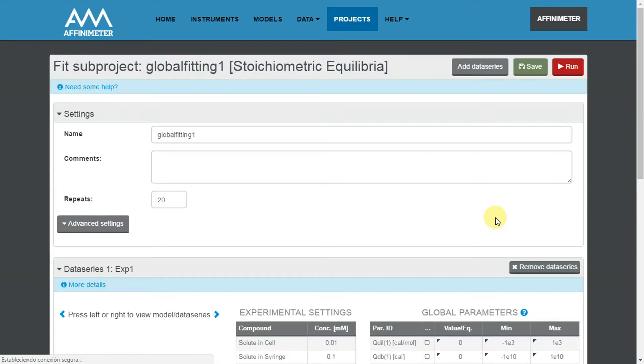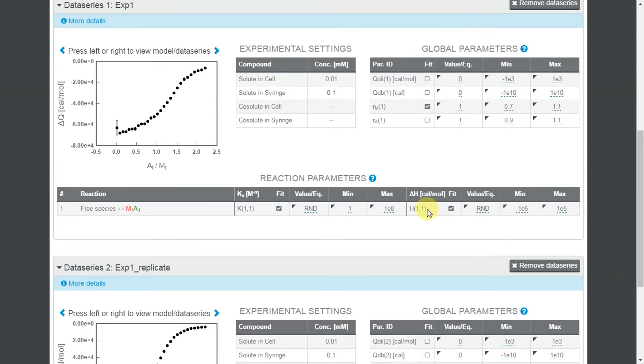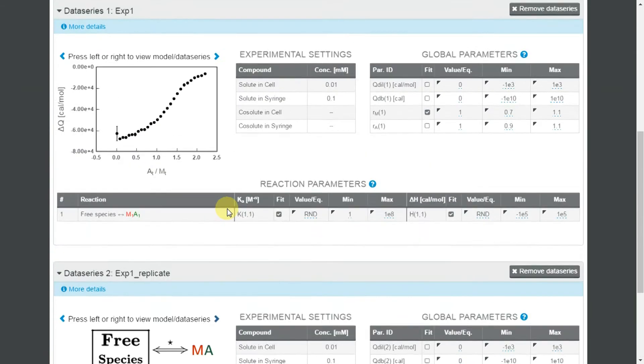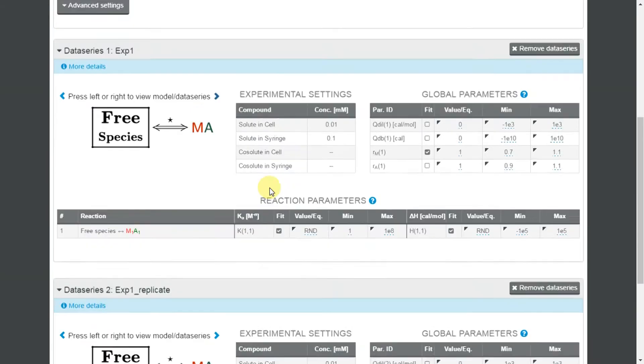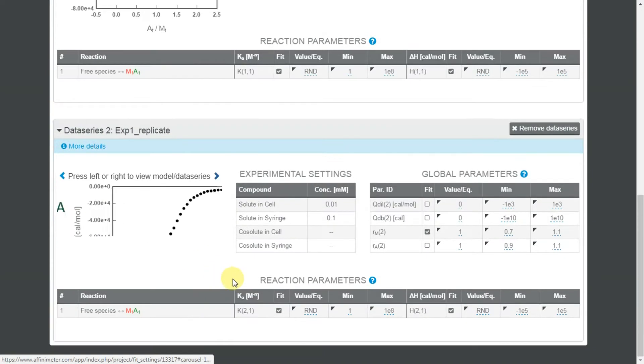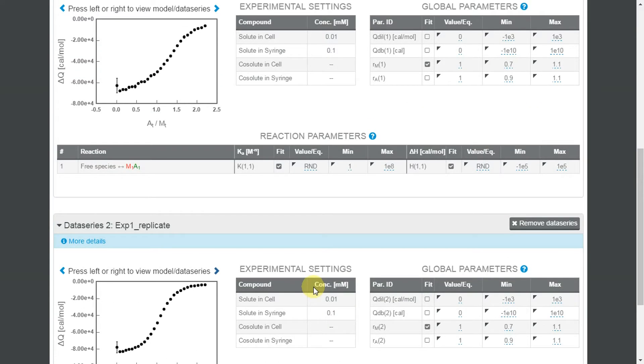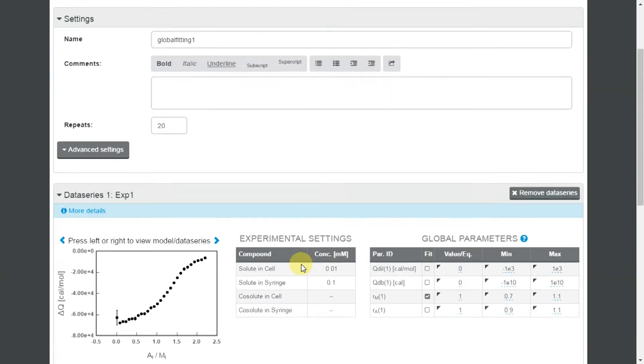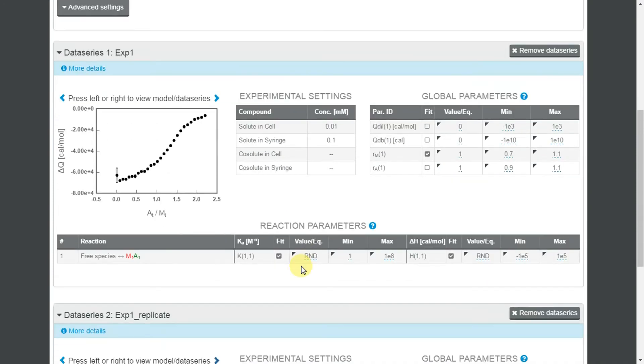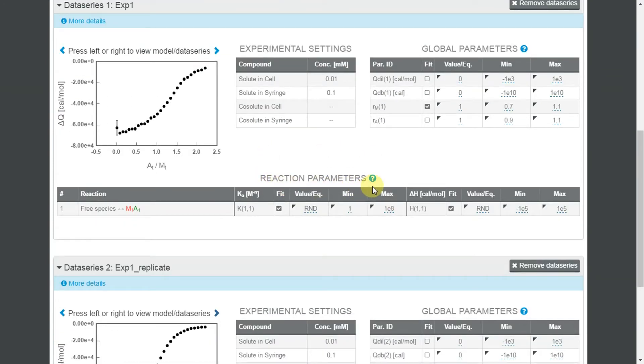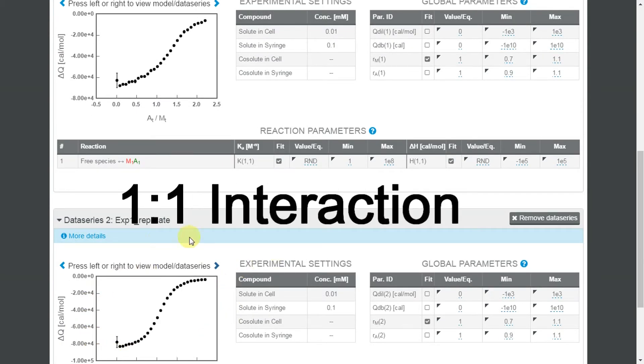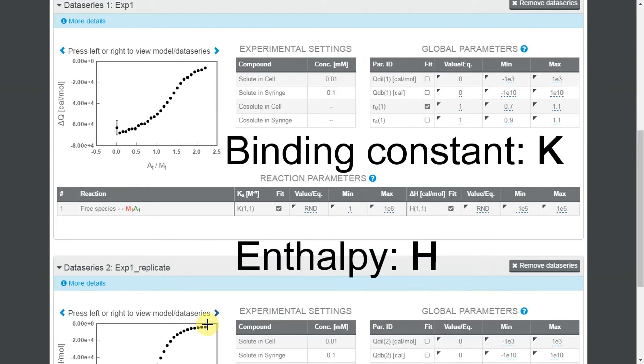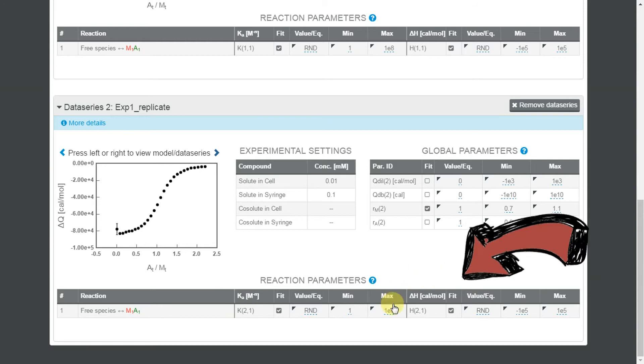So what we have in this project now is two isotherms, and these two isotherms correspond to the same binding interaction — so we are working with replicates. To do global fitting of these two isotherms, we have to determine which parameters are shared between isotherms. Since the two isotherms are describing the same binding event and it is a one-to-one interaction, the binding constant and the enthalpy of both isotherms have to be the same. So we are going to impose this restriction in the global fitting.